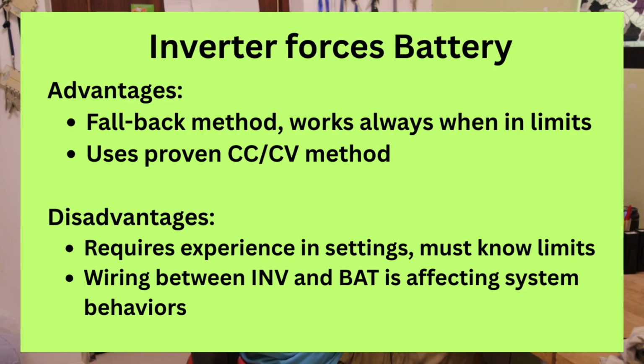Disadvantages of this method might be that it requires some experience, because you need to know what exactly you are setting in your inverter, and the BMS does not have to intervene and stop whatever you are doing. The other thing is, of course, that the wiring between your inverter and battery is affecting the system behavior. All the wiring is adding up resistances, and those will affect currents and voltages, voltage drops. So your CCCV method will be affected by those resistances there.